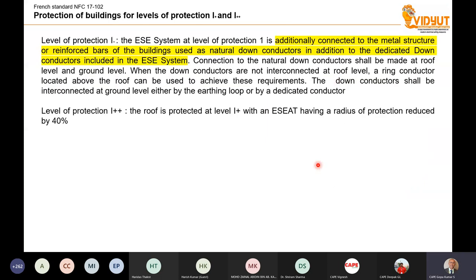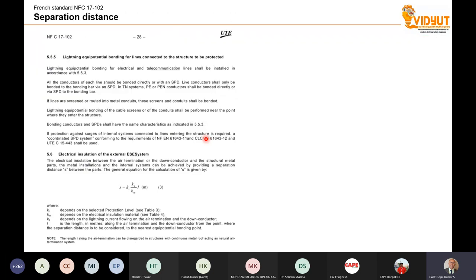Now, again, go back to the standard. Protection level 1 plus means the ESE rod is additionally connected to the metal structure or reinforced bar of the building, used as a natural down conductor in addition to the dedicated down conductor included in the system. This part says that if you want to increase the efficiency of your system, you have to connect your down conductor also to the structural steel. That means you use the natural component, which I explained in one of the previous slides. Whatever is explained in the IEC and the IS standards, they are repeating. Now, level of protection I++: the roof is protected at level 1 plus with an ESE having a radius of protection reduced by 40%. So these are the explanations in the standard.